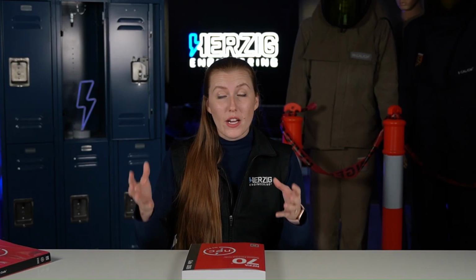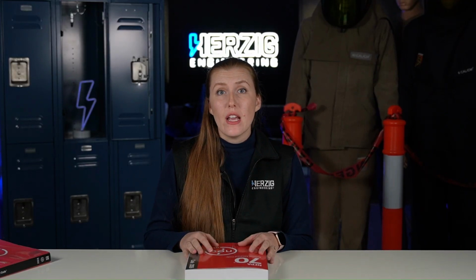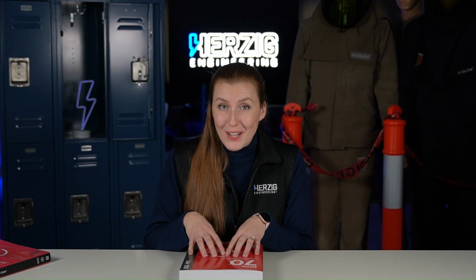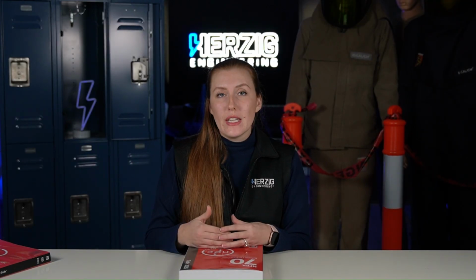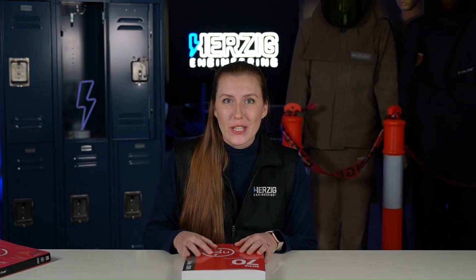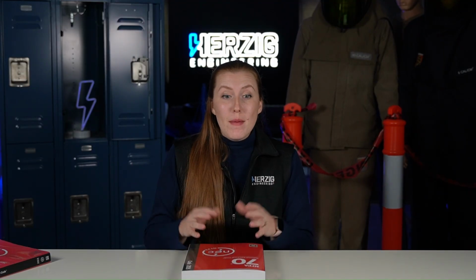But what about OSHA? If you remember, recently they came out with an arc flash guidance document and webpage and a lot of wonderful resources and information that honestly they point to complying with this requirement before the 2026 code even was released. So I will say OSHA, your local, city and state authorities, and the NFPA are all kind of aligning here, and it's incredible to see because previously there's been some gray areas and discrepancies, but with the guidance documents, with the 70E requirements, and now with the actual National Electrical Code clarifying these requirements as well, there's a lot more continuity between the regulations, which actually makes it easier for you to comply with it. You don't have to juggle and balance different initiatives and wording to make everyone happy. So I'm actually really excited to see this.